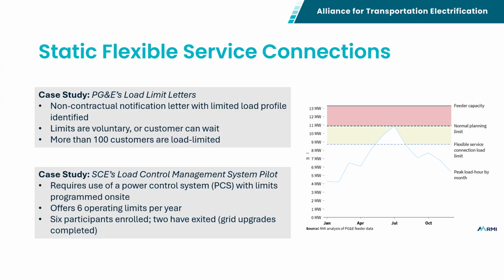Southern California Edison's pilot load control management system, or LCMS program, operates similarly. They actually require the customer to have a power control system on the site with the limits coded in and programmed into that power control system. PG&E doesn't require that, which is kind of an interesting approach. SCE offers 6 operating limits per year, so they select winter, summer, I think, and then shoulder seasons, and then each season has 2 operating limits throughout the day. So you've got your normal operating limits and then your constrained hour operating limits.